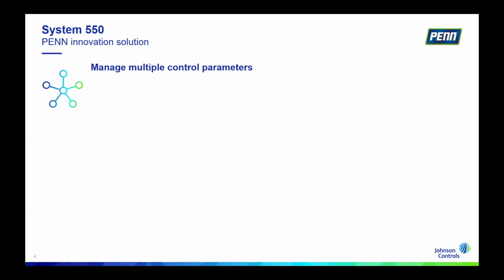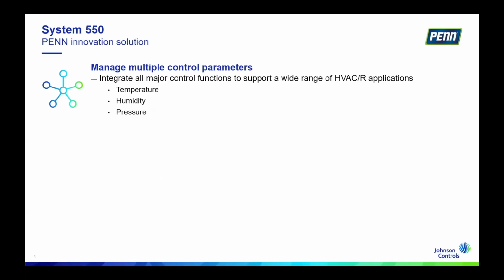I'll breeze through this slide a little bit because we'll talk about some of this in more detail in the coming slides. But essentially, System 550 can be used to manage multiple control parameters, any mix of temperature, humidity, and pressure inputs, and it's an expandable system. So your main module, your control module, starts with 2 relay or analog outputs, and then you can expand that 2 outputs at a time up to 10 relay or analog outputs.